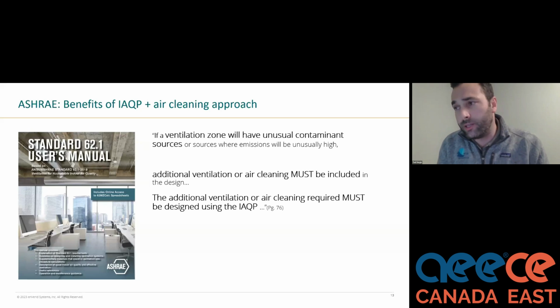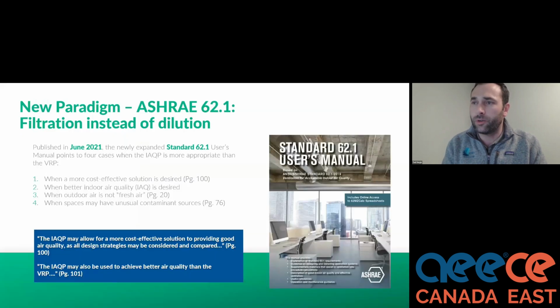When I first started 8 years ago at Inverid, the ventilation rate procedure was our default for ensuring acceptable indoor air quality. But now, if something weird happens, or if the space is weird, and there's unusual contaminant sources, then additional ventilation or air cleaning must be included, and additional ventilation or air cleaning must be designed using the indoor air quality procedure. So you're starting to see this publication of this pivot from your default being ventilation rate procedure to the indoor air quality procedure.